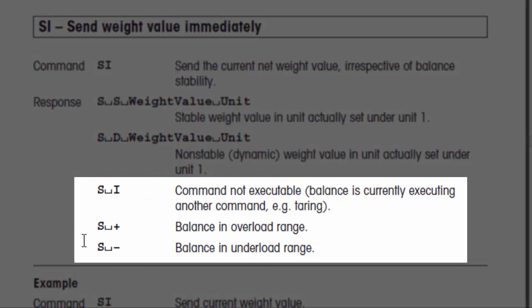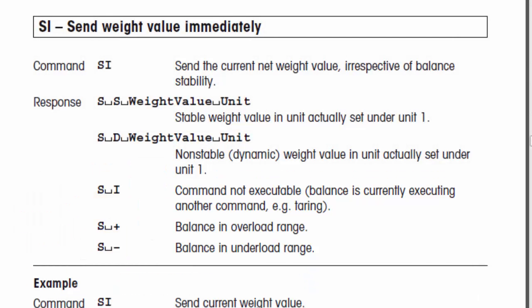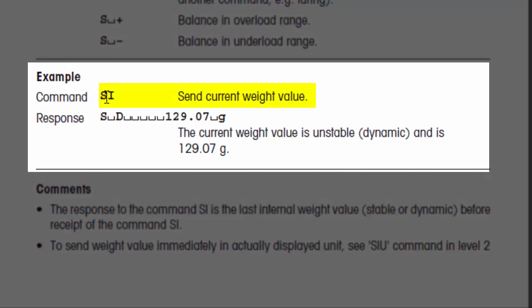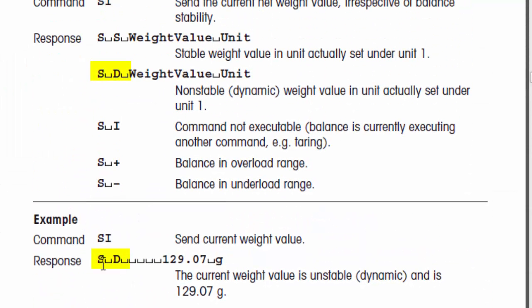There are also a couple of non-standard error-type conditions that could potentially be sent back from the scale, like if the command wasn't executable or if the balance was in an overload or underload range. We've actually accounted for those in the starter protocol, and I can show you what those look like shortly. One nice thing about this documentation is that it also gives you an example at the bottom showing what's being sent to the scale and a sample response. From that example, we can see an unstable weight response where the actual value is padded by spaces, which will also help us in how we code the message in Omni Server.